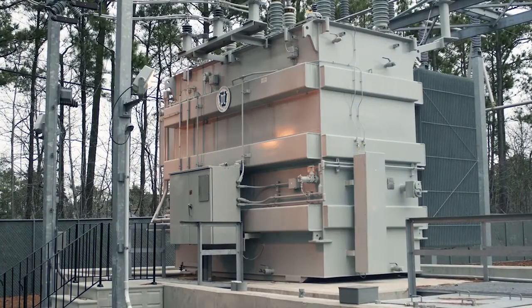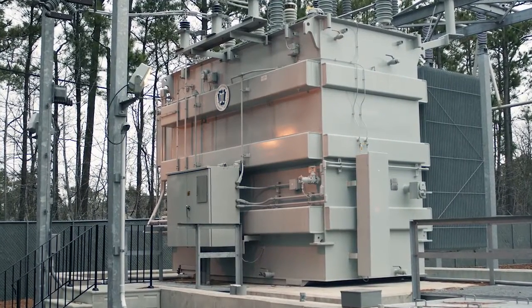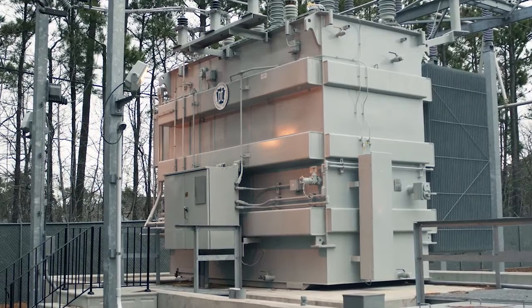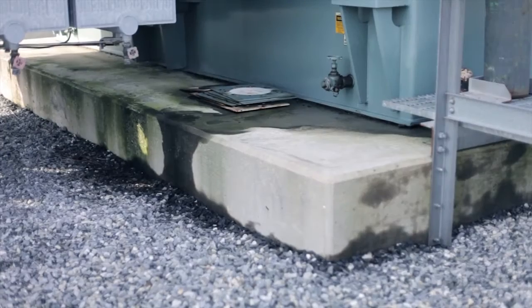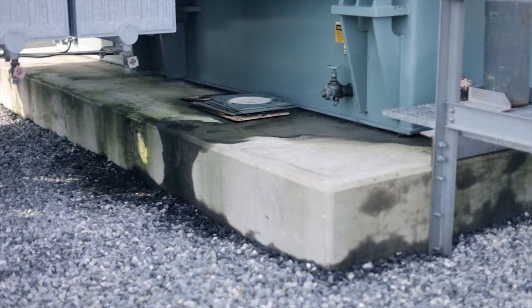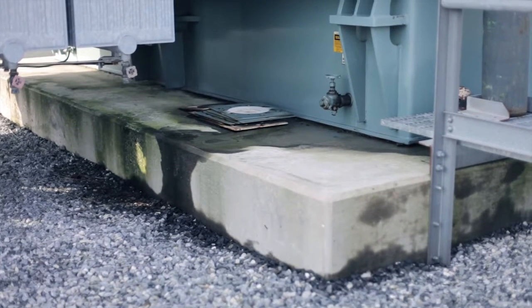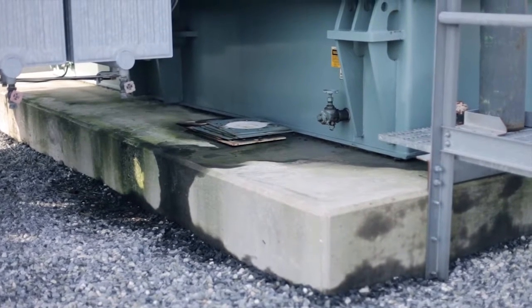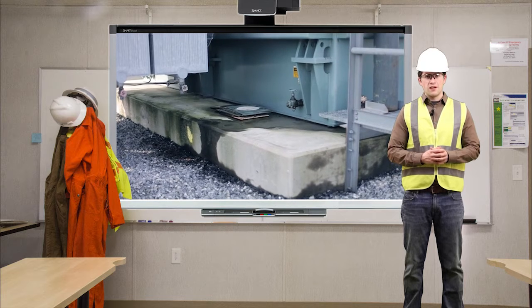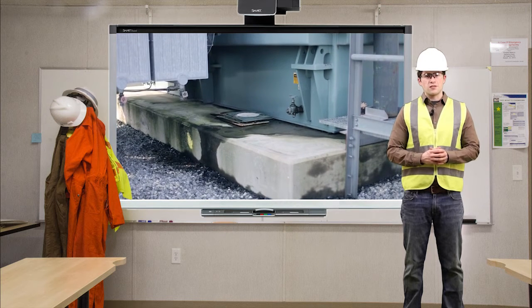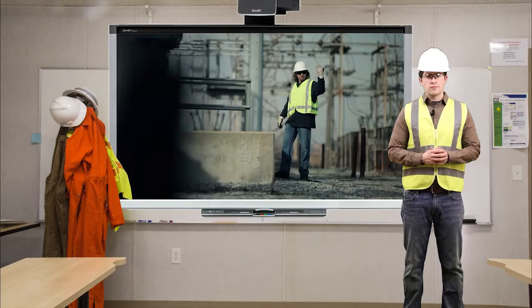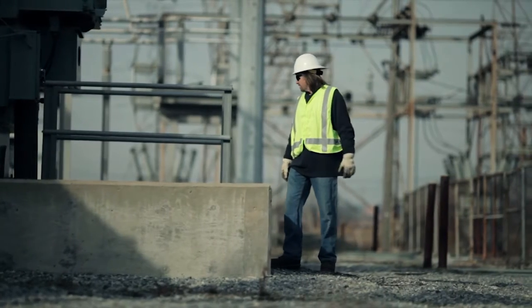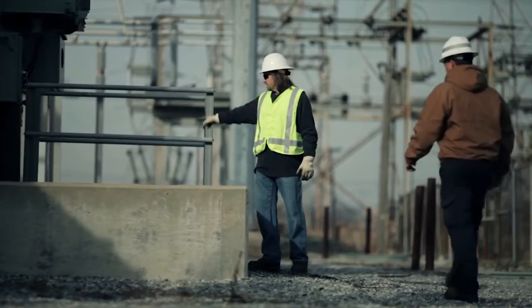New transformers, regulators, and PTs are insulated by a relatively harmless mineral oil. All oil spills should be avoided because some older equipment was filled with oil that could contain polychlorinated biphenyls, better known as PCBs. PCBs have been linked to cancer and other health problems. Report any unexpected exposure or contact to your PHI liaison.